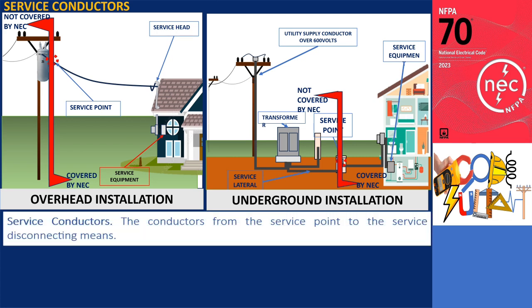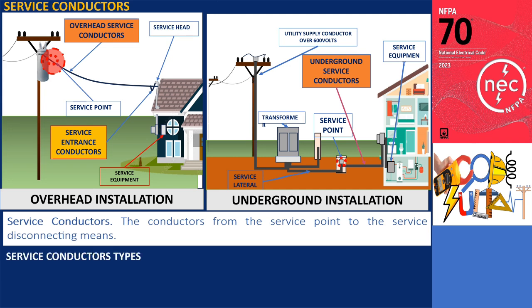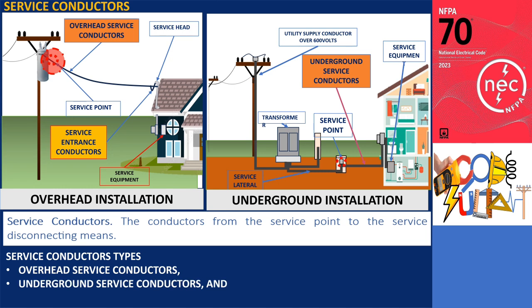The National Electrical Code covers only the conductors on the premises wiring side of the service point. These conductors are known as service conductors, as defined by the NEC, and they extend from the service point to the service disconnecting means. In the given illustration, the service point represents the connection to the terminals on the load side of a utility transformer. The conductor that runs from the service point to the service disconnect is specifically referred to as the service conductor. According to the NEC, the term service conductors encompasses various types such as overhead service conductors, underground service conductors, and service entrance conductors.